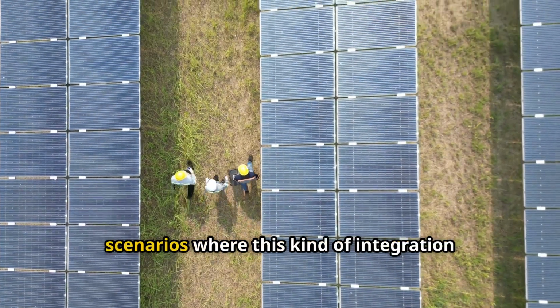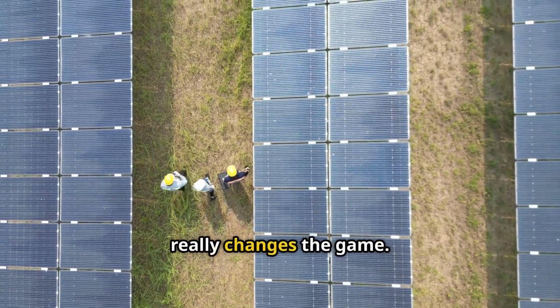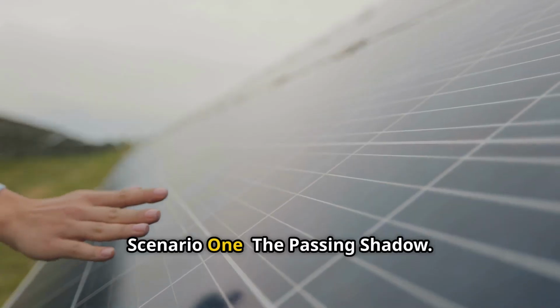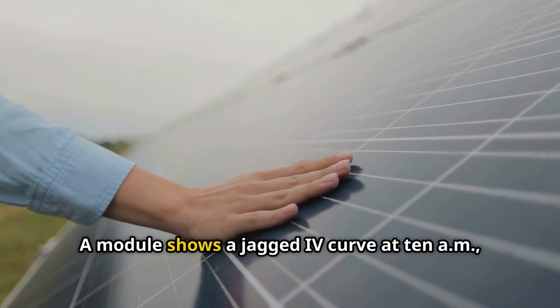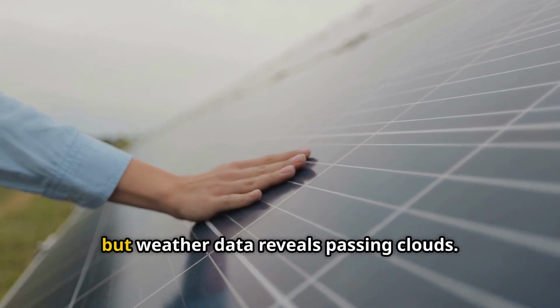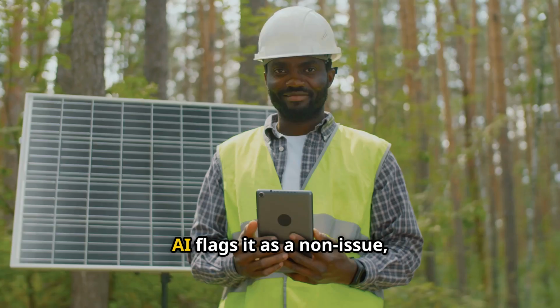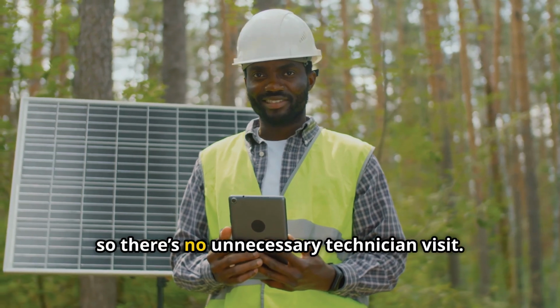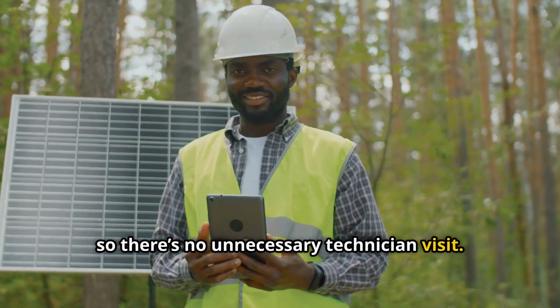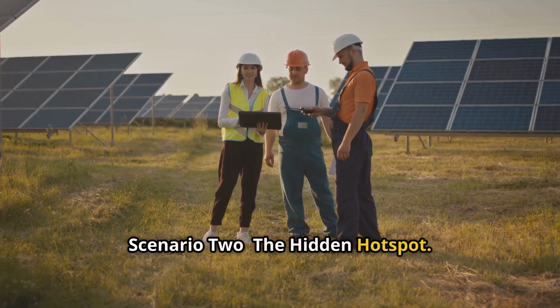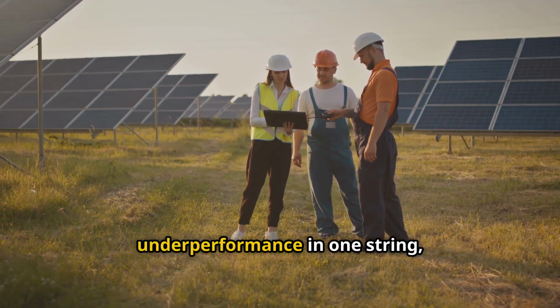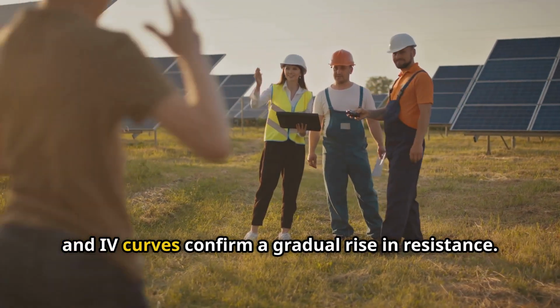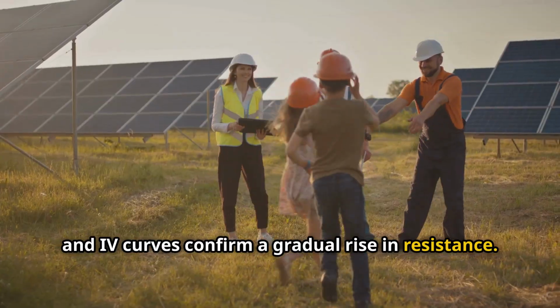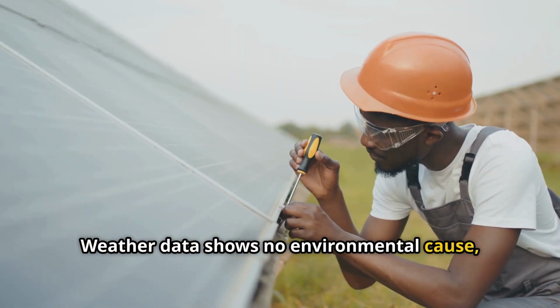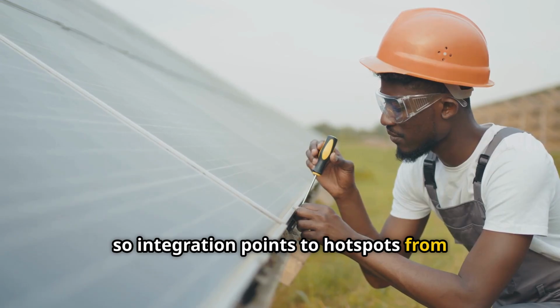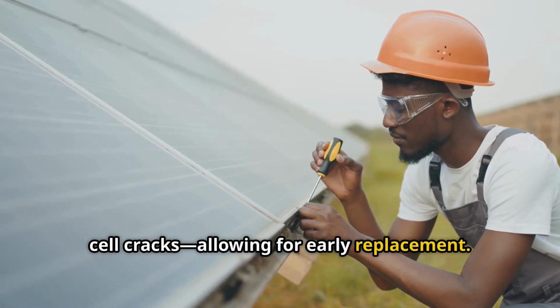Let's walk through some real-world scenarios where this kind of integration really changes the game. Scenario 1. The passing shadow. A module shows a jagged IV curve at 10 a.m., but weather data reveals passing clouds. AI flags it as a non-issue, so there's no unnecessary technician visit. Scenario 2. The hidden hotspot. Energy logs show consistent underperformance in one string, and IV curves confirm a gradual rise in resistance. Weather data shows no environmental cause, so integration points to hotspots from cell cracks, allowing for early replacement.